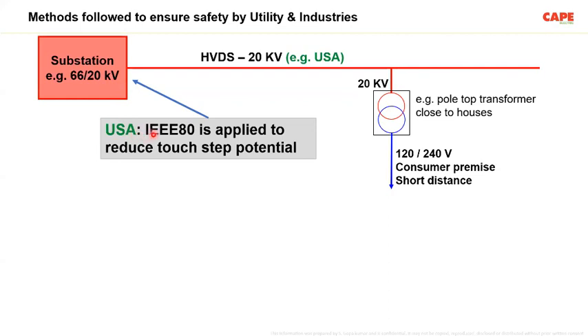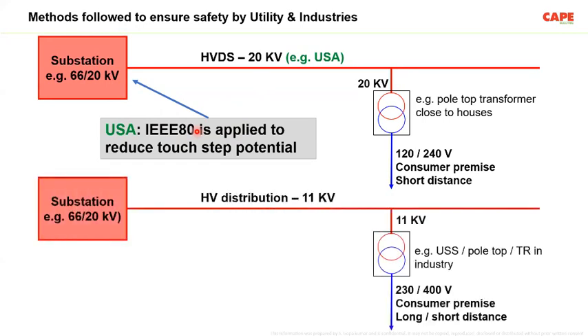In this substation, they make the touch and step potential reduction measures as per IEEE 80. This is a very good system because the definition is very clear. They know what a substation looks like, they know their system, and they do the best. The touch and step voltages are reduced based on IEEE 80. And now the problem which we face is our system is a little bit different from their system. I'm sorry, I have put 66 by 20 kV. This is actually a cut and paste mistake. You can think that it's an 11 kV.